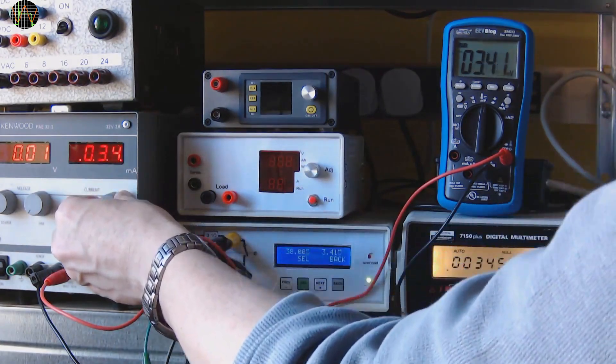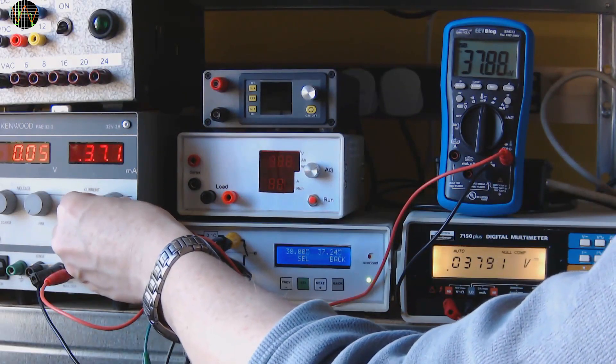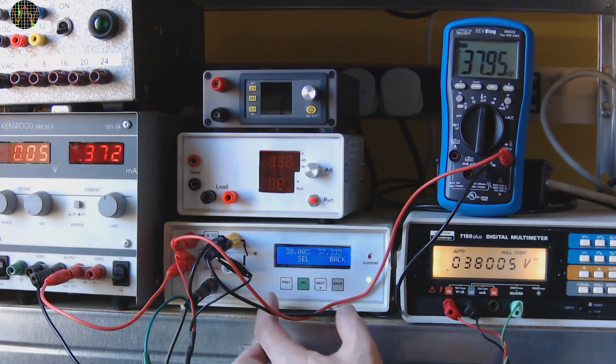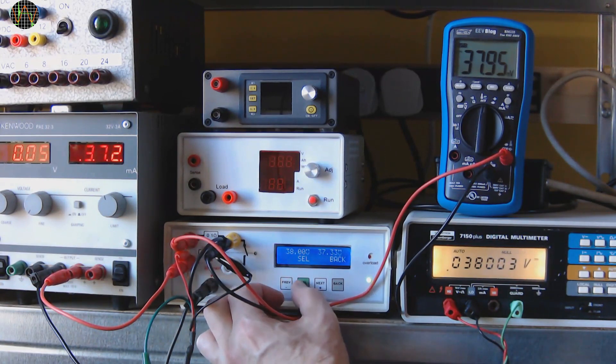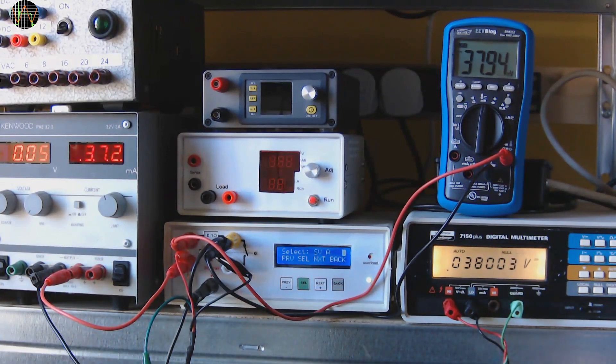These are incidentally 5% and 95% of the range. Adjusting is quite fiddly and can take a long time so for brevity in this video you see me accepting values that are slightly out. Pressing SEL finishes the calibration for shunt voltage A.